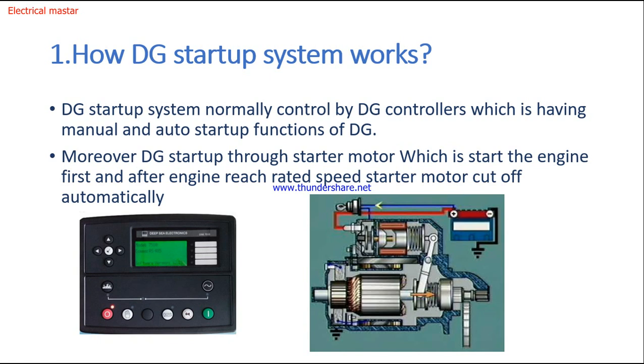The DG starts through a starter motor, which cranks the engine first. After the engine reaches rated speed, the starter motor cuts off automatically. With the help of the starter motor, once the generator engine reaches the rated speed of 1500 RPM, the starter motor cuts off automatically.